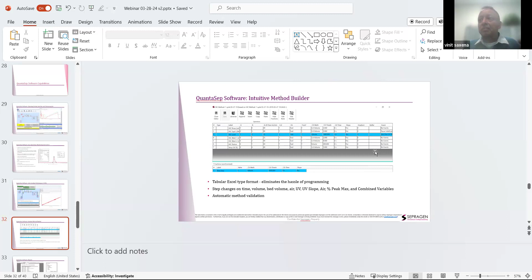And all kinds of reports, right? So method report, user report. We have different levels of users that can log on to the machine. Some people have permissions only to run methods. Other people have permissions to make methods. Metrology folks, for instance, can only do calibrations, which are done from the system, the high and low points of all the sensors. Or event reports and journaling, right? It's very important that if there's data that's deleted, you track all that for 21 CFR Part 11 compliance.